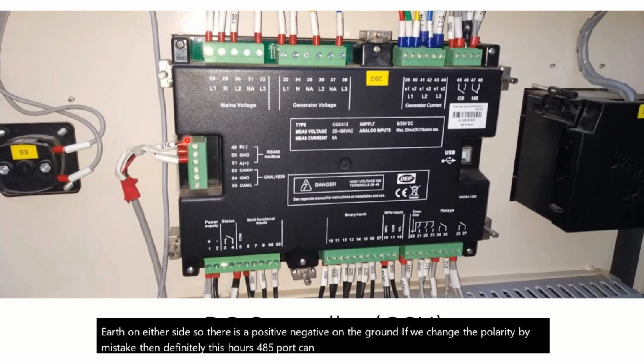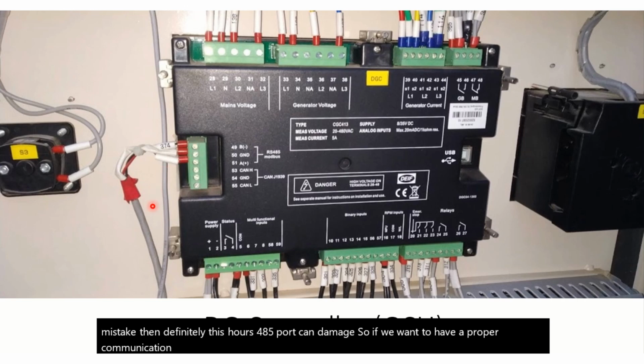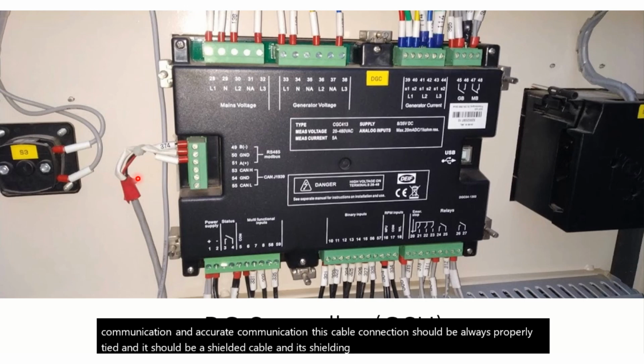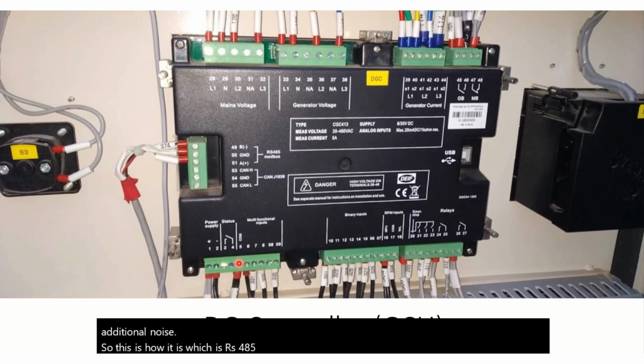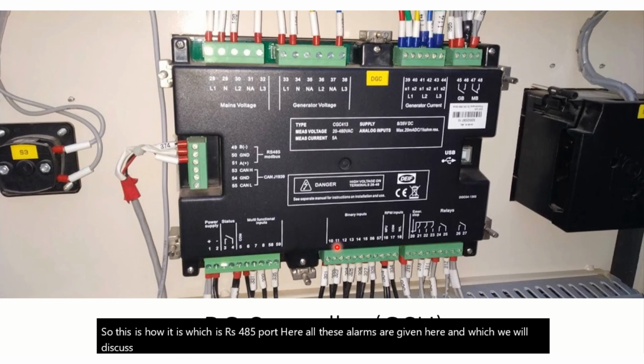If we change the polarity by mistake, then definitely this RS485 port can be damaged. So if we want proper and accurate communication, this cable connection should always be properly tied, and it should be a shielded cable, and its shielding should always be earthed to remove any additional noise. So this is how it is, which is an RS485 port. Here all these alarms are given, and we will discuss them in our subsequent module, section 4.